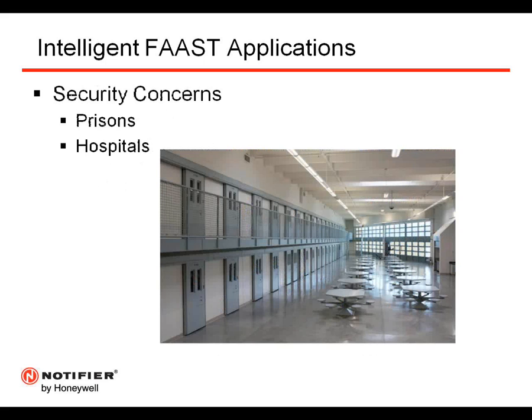Also, security concerns, whether it be a hospital or a prison. We see a fair amount of aspiration installed in the prisons because a lot of times in the cells, the inmates could either potentially tamper with or damage those spot-type smoke detectors. So by using an aspiration-type network, it allows them to run that pipe network in, and it's much more hidden, where the inmates cannot tamper with or damage those detectors. They can't damage the pipe network. And with this, I'm going to turn it over to Steve, who's going to run through some case studies for FAAST.